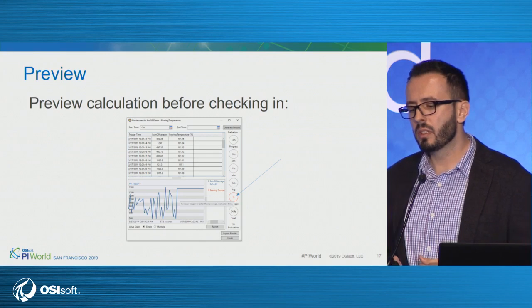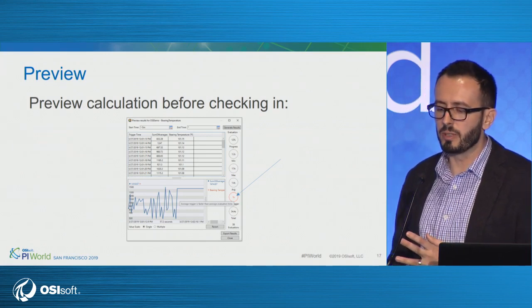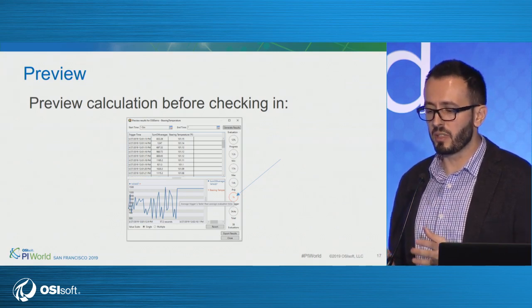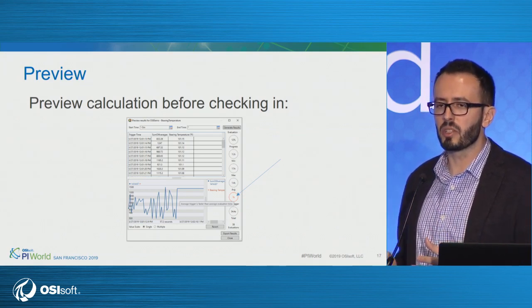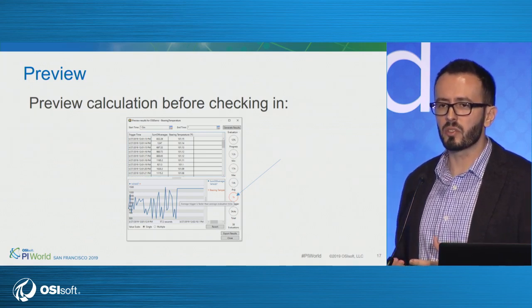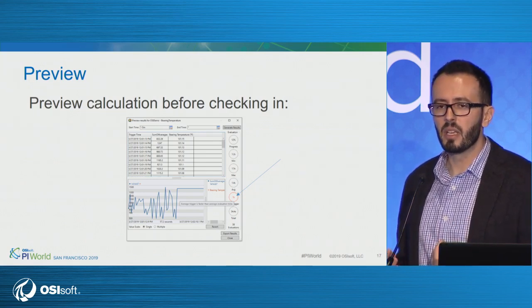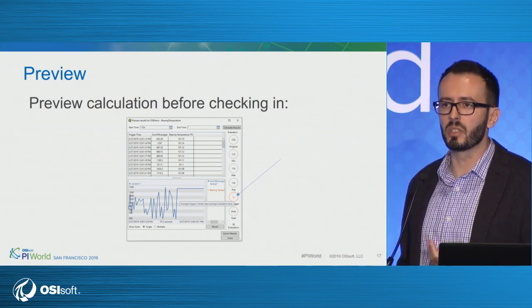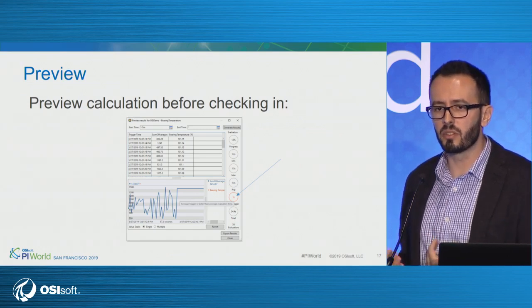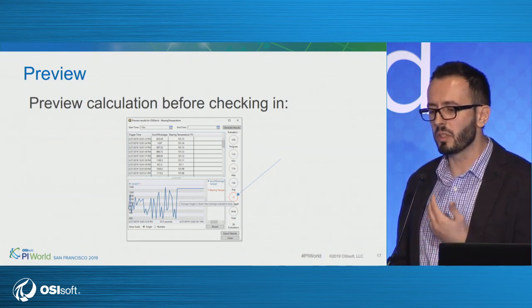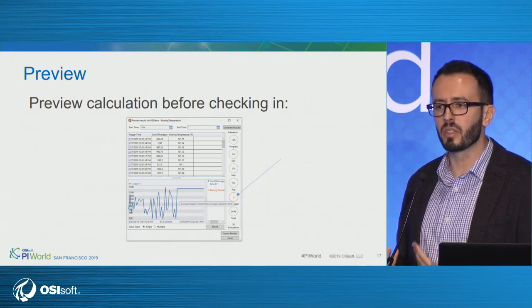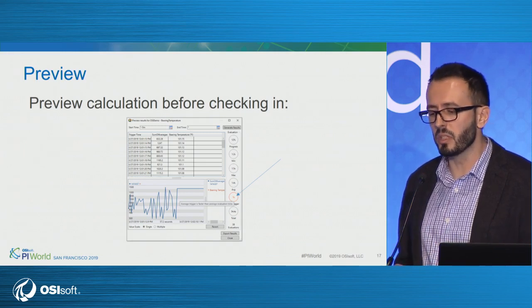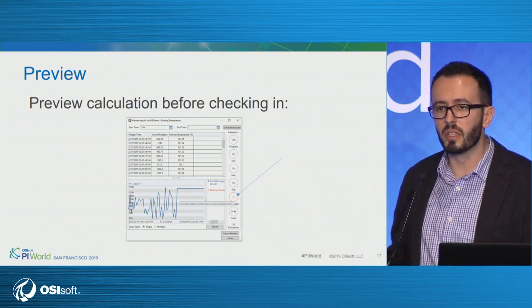Similar to evaluation, we really recommend also doing a preview on your calculation. You specify a time range in the past, and using your inputs in your calculation, you get to see how your calculation is doing going back in time. This is useful because if you were to do a backfilling or a recalculation using your new calculation, this is what would happen in the past. So this is the data that will be written. You want to see if it actually makes sense for the calculation that you have written. In addition, if there are any errors, you'll get to see them here as well, and you get to see a nice trend of your data.